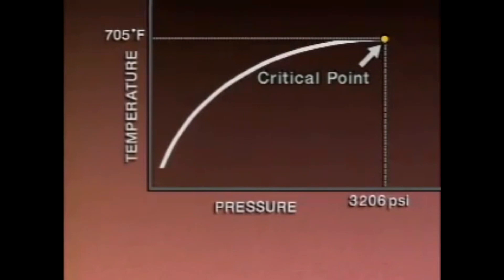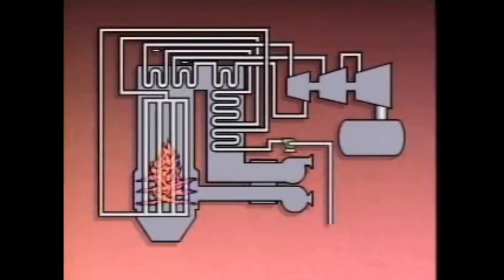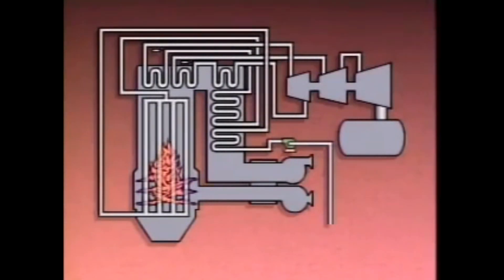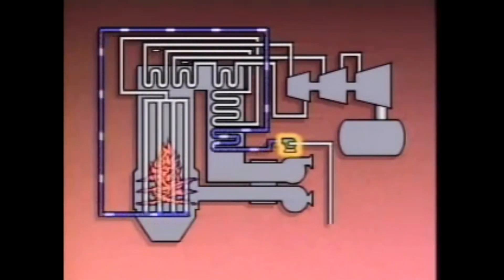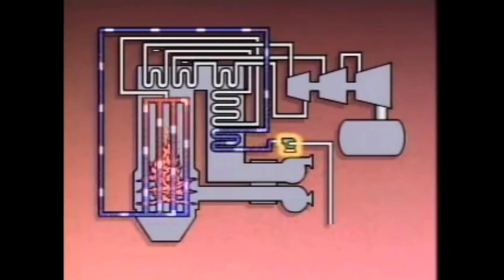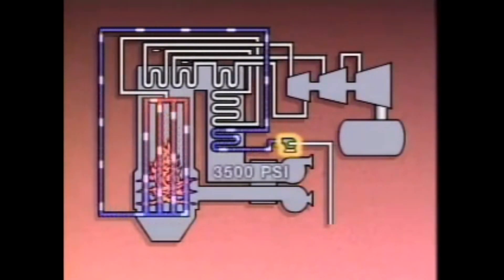A once-through boiler gets its name from the fact that water is pumped through it only once — it is not recirculated. Many once-through boilers are operated at supercritical conditions. In a typical supercritical once-through boiler, boiler feed pumps force the feed water through a header at the bottom of the furnace and up through the water walls. As the water flows through the water walls, its temperature increases. The water in the water walls is already under a very high pressure, typically around 3,500 PSI.